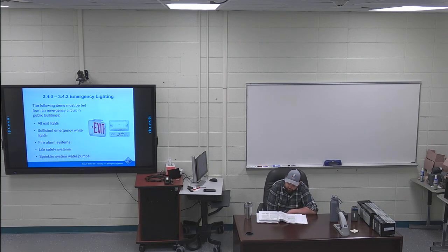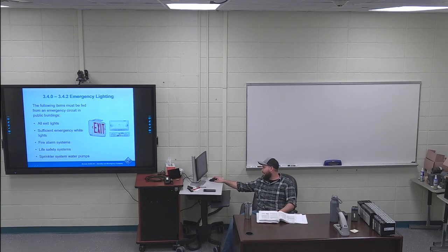Page 25, moving on to 3.4.1, the battery-powered emergency lighting. First full paragraph on page 25, first two sentences are highlighted. Specific requirements for emergency lighting are defined in NEC section 700.15 through 700.26. The required backup time for batteries for emergency lighting is an hour and a half, which is 90 minutes, although some systems may be designed to have a longer backup time. So if you got batteries that are turning on your emergency lights, they have to last for at least an hour and a half. All these little lights, like up here on the board, have little batteries in them. They should be able to stay on for an hour and a half.